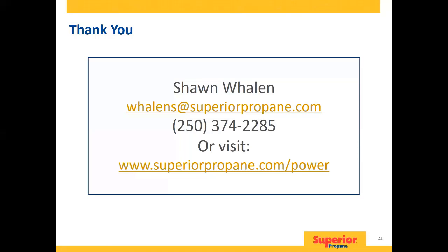To answer your questions about cold weather concerns, there are two ways we supply propane to a power generator. One, we can pump the propane over to vaporizers mounted on the engine, which uses the hot water coolant to vaporize the propane as it arrives at the generator in its liquid state. Otherwise, for smaller generators, especially in a northern climate, we may vaporize the propane at the site using what's called a propane vaporizer, which creates heat and turns the propane from liquid to vapor to feed the generator. Predominantly though, on the large generators, we're pumping it over in its liquid state.